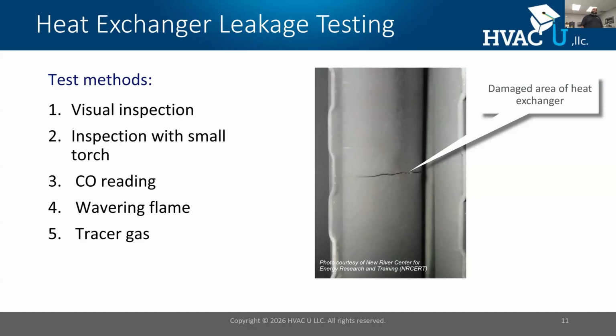This is an actual heat exchanger failure, where if I have a furnace that is underducted, it's going to short cycle. And what happens when furnaces short cycle? The metal inside the heat exchanger starts to anneal. If you think about when you were a kid, maybe you had a piece of plastic and you bent it back and forth several times. What happened? The plastic eventually broke. That's what happens when you have an inadequate duct system. The air can't leave the furnace bonnet efficiently enough, and it's going to short cycle, oftentimes on high temperature limit. The metal heats up and cools off, it's annealing, and eventually it's going to break. And when it breaks, we get a situation like this.